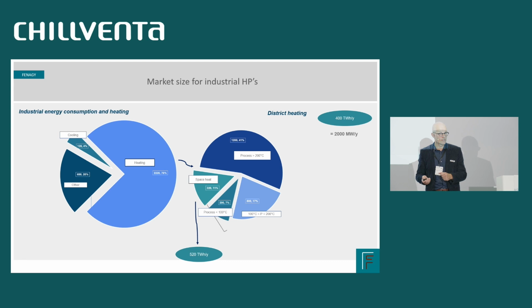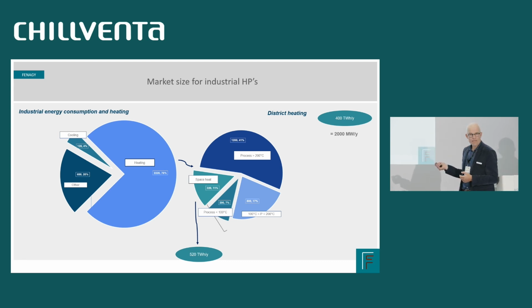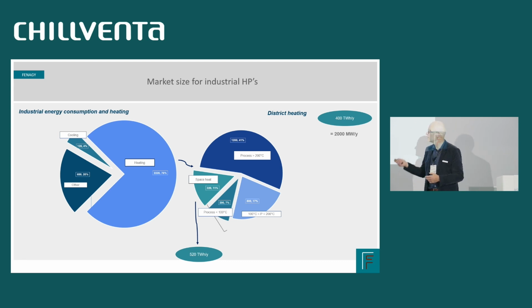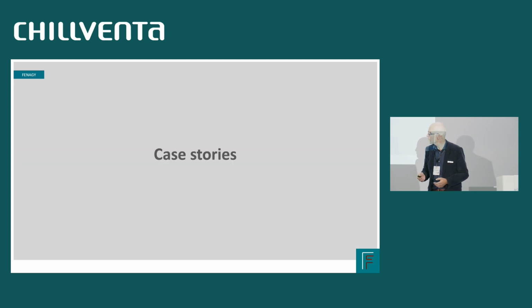Then we have the more difficult applications. That is high temperature heat pumps, from 100 to 200 degrees, and the really high temperature heat pumps, which is probably not available right now, but somebody is working on it, above 200 degrees. There's a huge potential there. That is if we want to decarbonize the whole industry. So the potential is really, really big here for heat pumps.